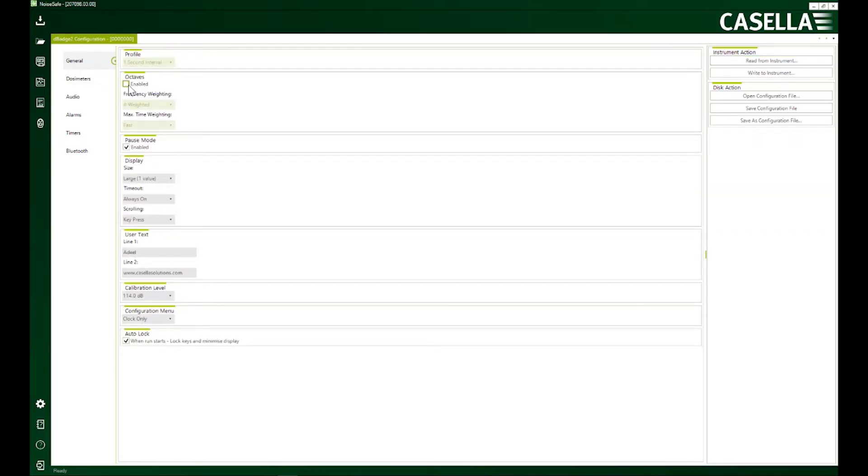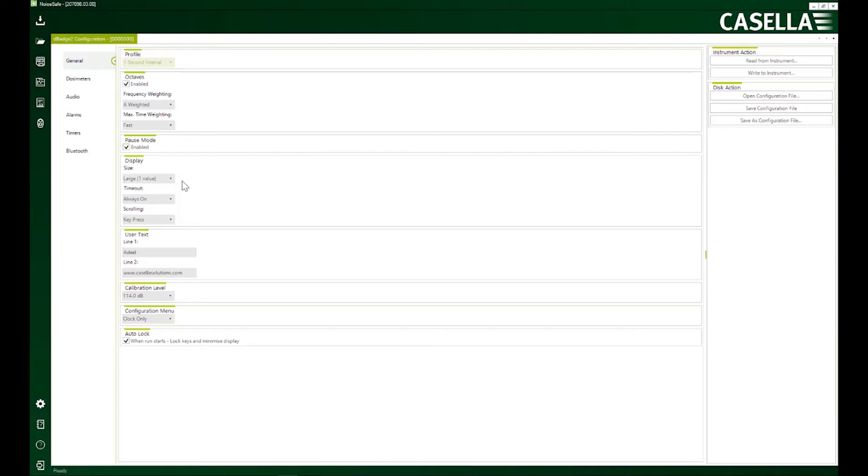So here I can enable and disable octaves. If I enable them I'll be able to change the frequency and time weightings. I can enable or disable the pause mode. Enabling this mode would allow me to filter out any unwanted noise in my readings. So I can always pause or take out any noise which I do not want in my readings.